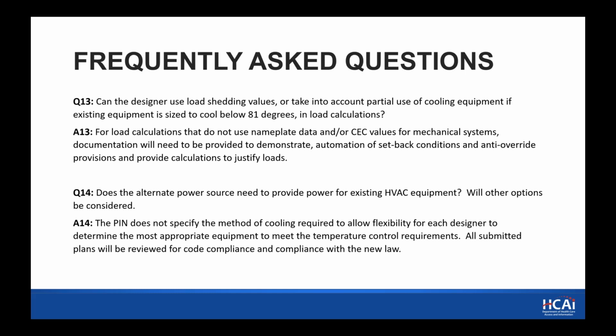I don't know that there's a lot to be gained from not putting the entire system on, but if that's the approach, then you'd need to validate that the system won't be drawing nameplate rated values. Question 14. Does the alternate power source need to provide power for existing HVAC equipment or can other options be considered? The PIN does not specify the method of cooling required, to allow flexibility for each designer to determine the most appropriate equipment to meet the temperature control requirements. All submitted plans will be reviewed for code compliance and compliance with this new law.